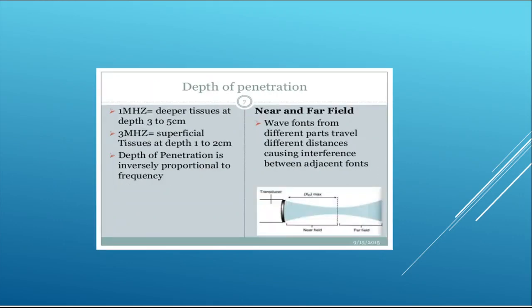For depth, let us talk about the depth of penetration. This is 1 MHz for the deeper tissues at a depth of 3 to 5 cm, and 3 MHz is for the superficial tissue at a depth of 1 to 2 cm. The depth of penetration is inversely proportional to the frequency. So if there is an increase in the frequency, the depth of penetration is less.